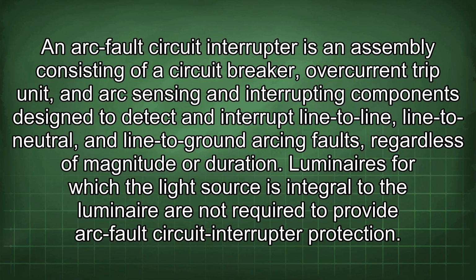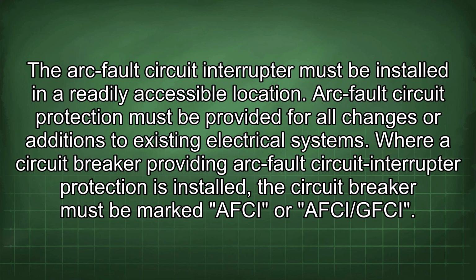An arc fault circuit interrupter is an assembly consisting of a circuit breaker, overcurrent trip unit, and arc sensing and interrupting components designed to detect and interrupt line-to-line, line-to-neutral, and line-to-ground arcing faults, regardless of magnitude or duration. Luminaires for which the light source is integral to the luminaire are not required to provide arc fault circuit interrupter protection. The arc fault circuit interrupter must be installed in a readily accessible location. Arc fault circuit protection must be provided for all changes or additions to existing electrical systems.